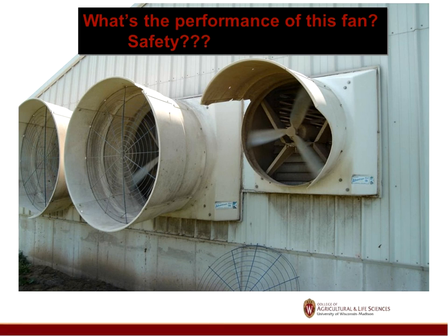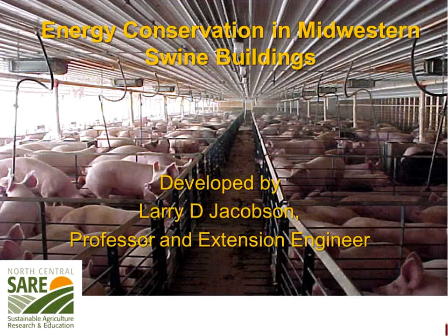Here's a discharge cone that's gotten damaged, so we've got a safety issue because now the guard can't be put in place, and we've got open blades here. So from a safety standpoint and a performance standpoint, it's very important to keep the maintenance up and think about safety. So now we'll move to swine and look at some of the issues with swine buildings.